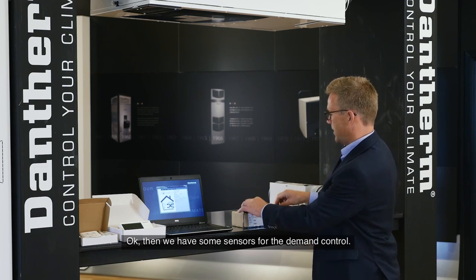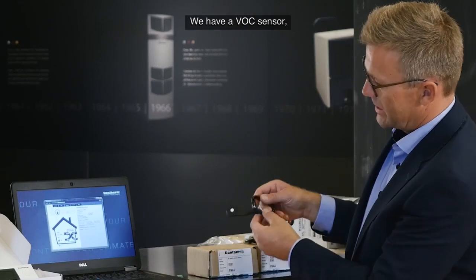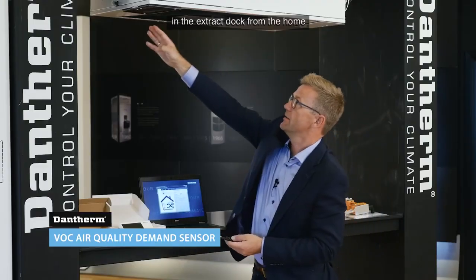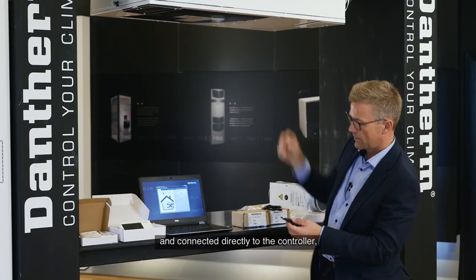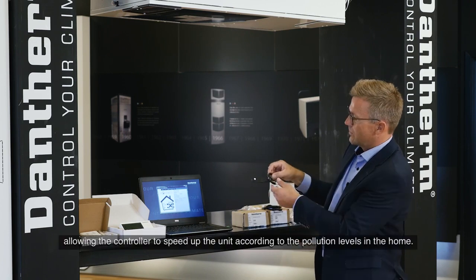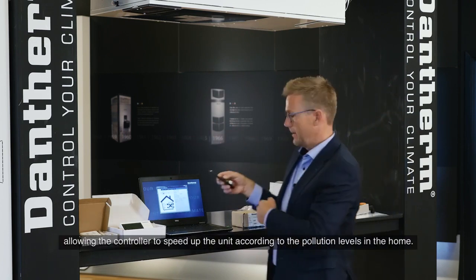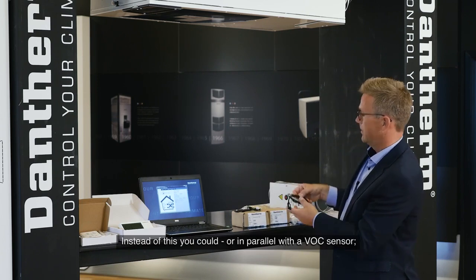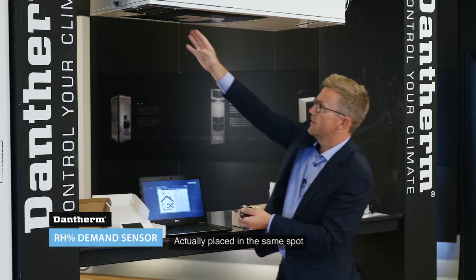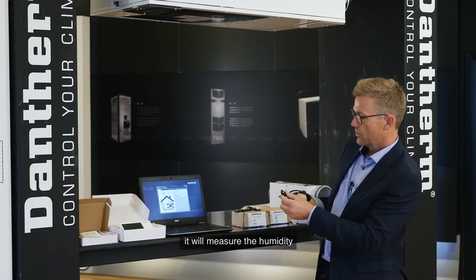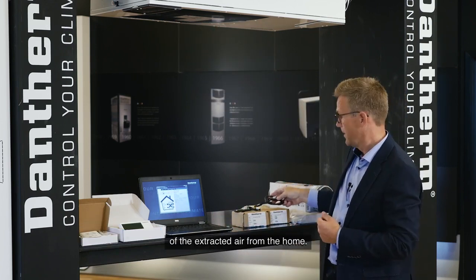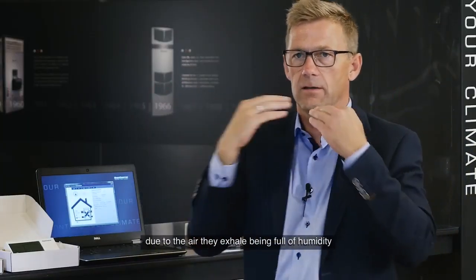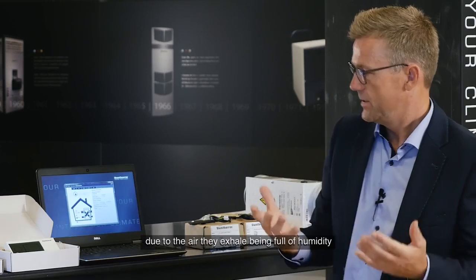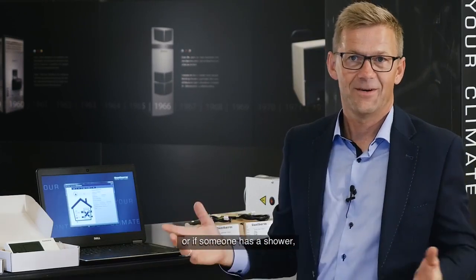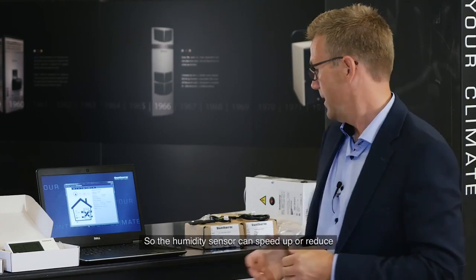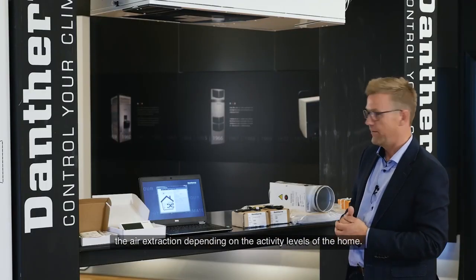Okay, then we have some sensors for demand control. We have a VOC sensor, which can be mounted here into the extract duct from the home and then directly connected to the controller. Then the unit will speed control after the air pollution in the home. You could also, instead or in parallel, use a humidity sensor placed on the same spot in the extract duct, which will measure the humidity in the extract air from the home. The humidity will rise when there are a lot of people in the home because of breathing, and also when they take a shower, they will produce some condensate in the home. Then the unit will speed up and down depending on the activity level of the home.